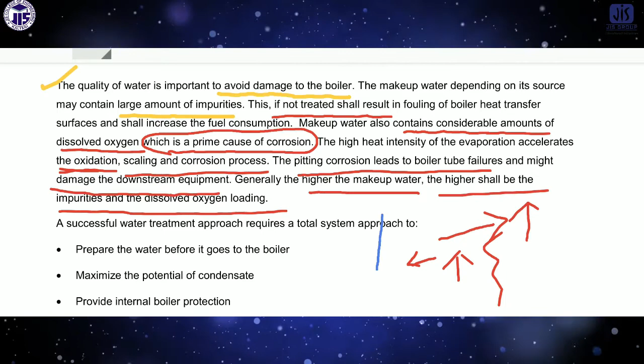Second step, maximize the potential of the condensate. Third point, provide internal boiler protection. Maintain clean internal boiler surfaces. This is a very important point. The internal boiler surface should be clean. If it is not clean, then the heat transfer will not be equal. What I told you a few minutes ago: if heat transfer is not uniform, there is a high chance of explosion. Then avoid problems and shutdowns, extend equipment life, and monitor and control the treatment level.